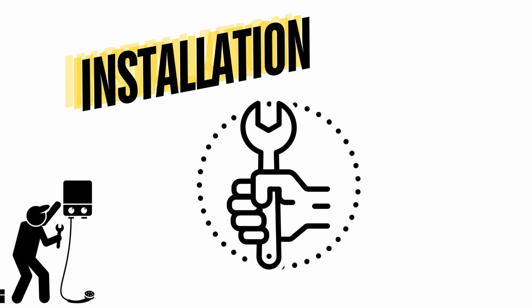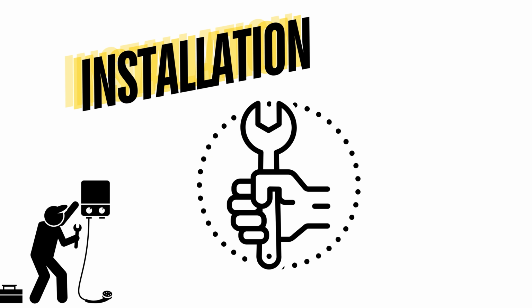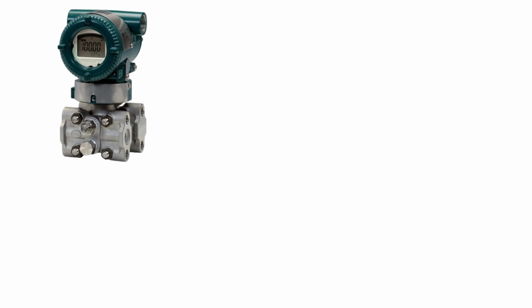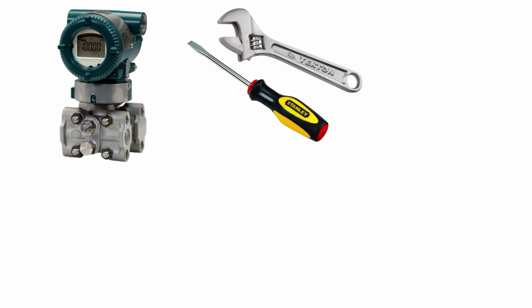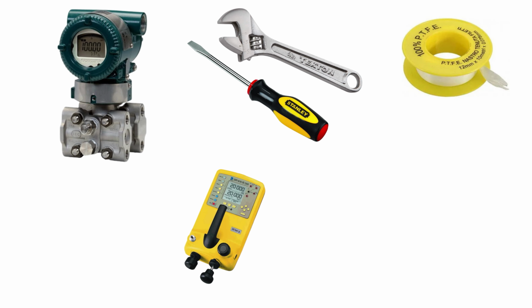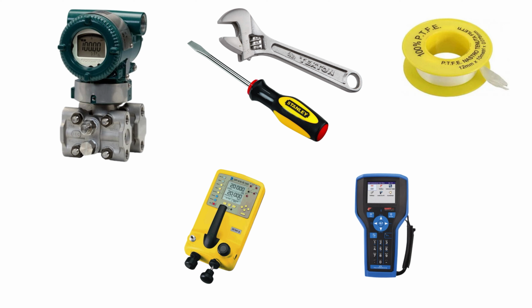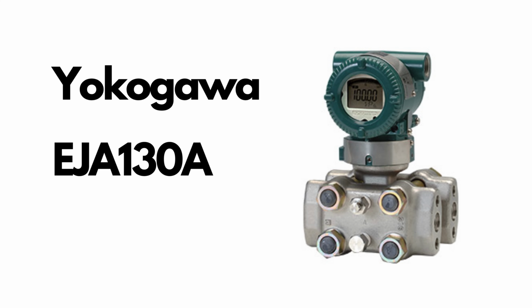Now, let's get to the installation. Before we start, here are the tools and materials you'll need. A differential pressure transmitter, wrenches and screwdrivers, Teflon tape, calibration equipment like a pressure calibrator and HART communicator. Let's get into the installation process. Here's how to do it step by step. We will take the example of Yokogawa Model EJA130A.